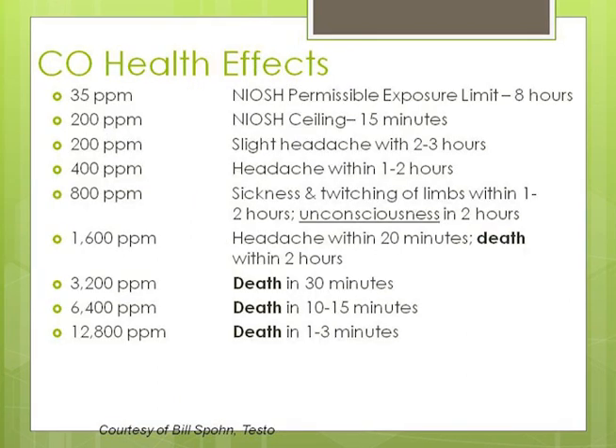At around 400 parts per million, carbon monoxide starts to affect you fairly soon — within one to two hours you'll get a headache. If you double that, you get sickness and twitching of limbs, and when it's really strong, it can kill you in three minutes. The most I've ever read on my meter was around a thousand — that's the max it went — and we just got out of there.